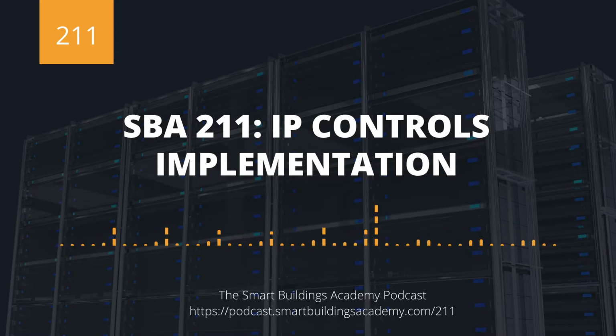Now, on the flip side, we are seeing several manufacturers come out with these IP controllers that have field trunks built into them. So I've got some Edge 10s on my wall over there, and those actually have field trunk capacity. They have supervisory capacity. They're running Niagara inside them, so they act as a supervisory device essentially. And so you're seeing that.